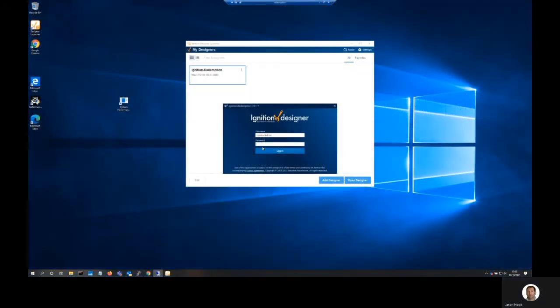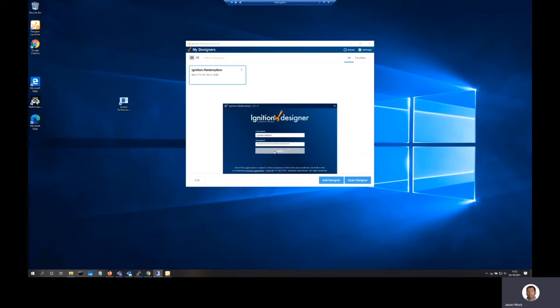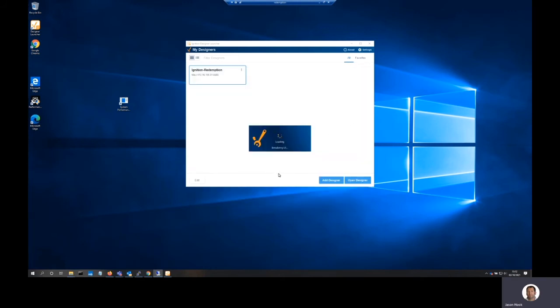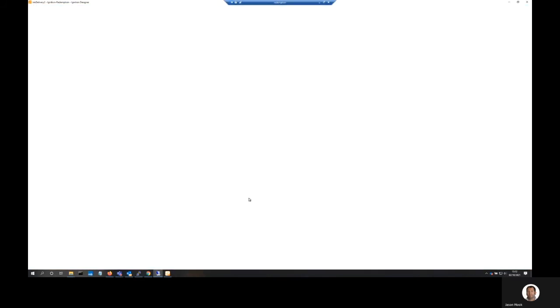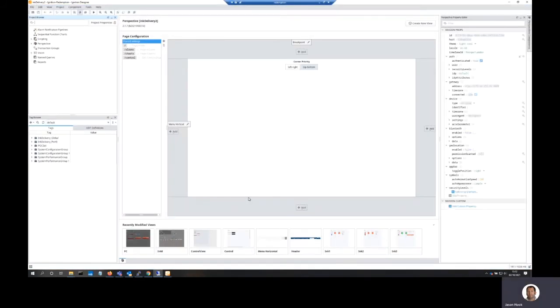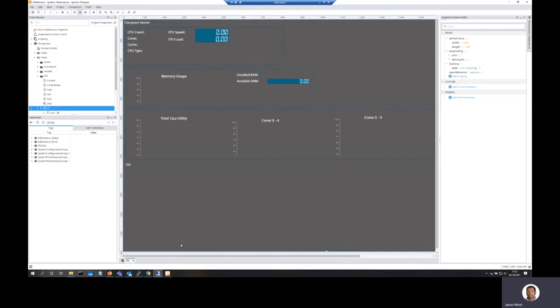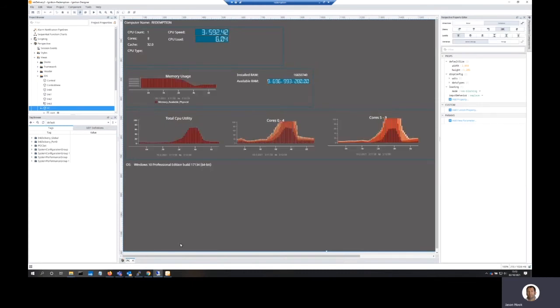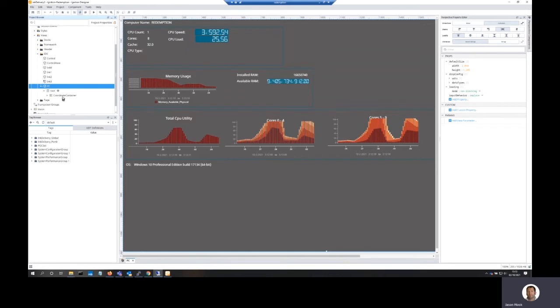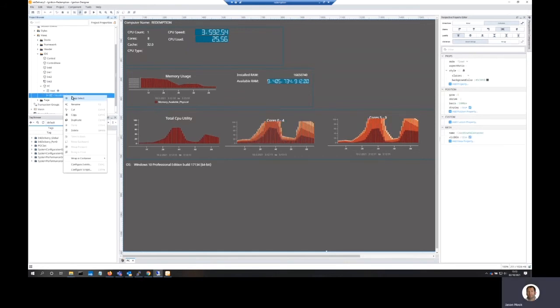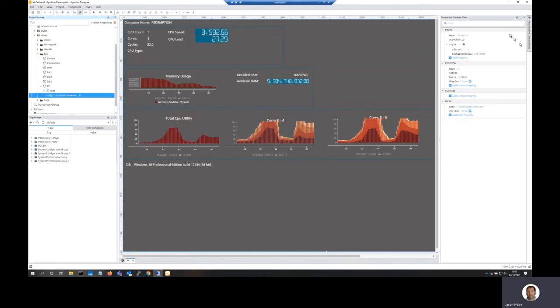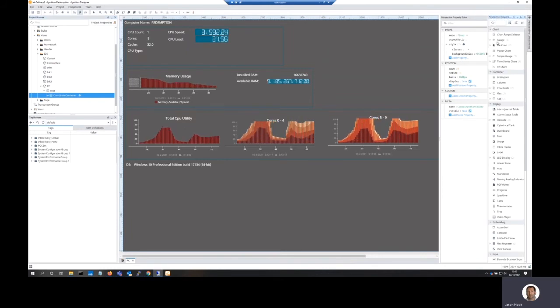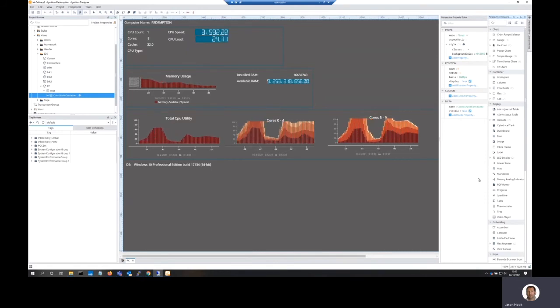So we're going to have a look under the hood of this SCADA application and add some data. I just need to log in and open the designer client. InkDelivery2 is the project that we're working on. And this is the designer client. The application is comprised mainly of views. And those views contain components. And those components are connected to OPC UA tags. The data from that comes from the OPC UA server. So the application we're going to modify here, or at least the part of the application we're going to modify here is the one that we've been looking at, which is the PC data from the Harlequin Direct PC. And so what I'm going to do is I'm going to add a piece of data to this page. And we'll take you step by step through doing that.